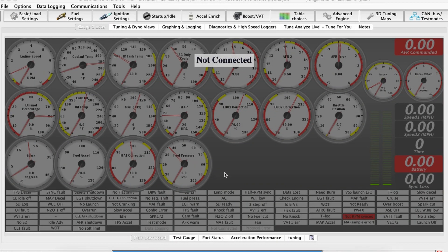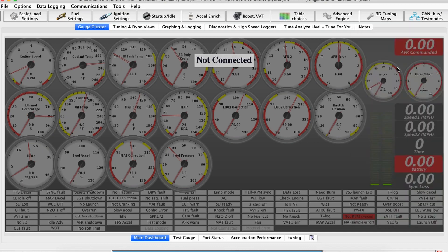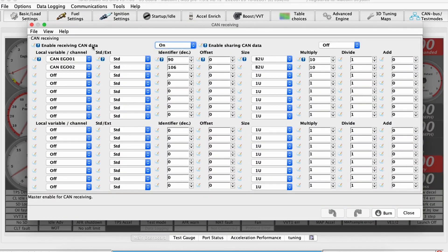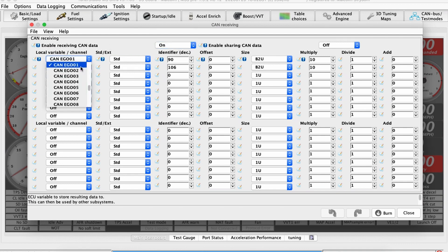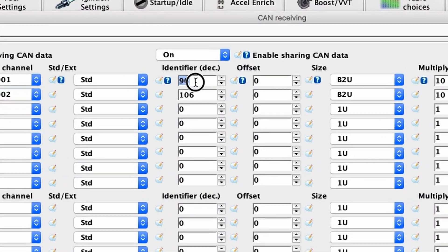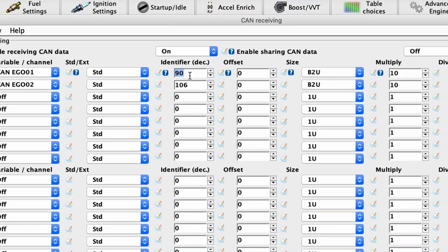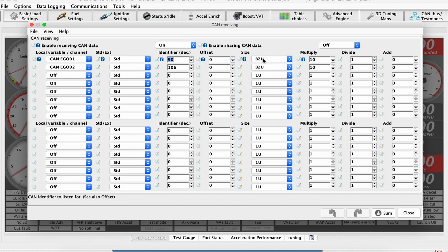Now let's cover the MS3 configuration so we have it all in one place for easy reference. Go to CAN bus, then CAN receiving. Make sure 'enable receiving CAN data' is turned on. We're going to set up EGO1 and EGO2 — those are defaults. Under the identifier, reference back to when we set up the widebands at 5A and 6A in hex. These fields are in decimal, so as long as you copied those same numbers, you're fine. If you need to convert hex to decimal, just use Google. Set both to B2U, multiply by 10, and leave the rest as defaults — 1 and 0. That takes care of that screen.